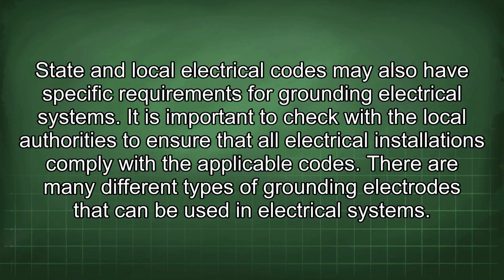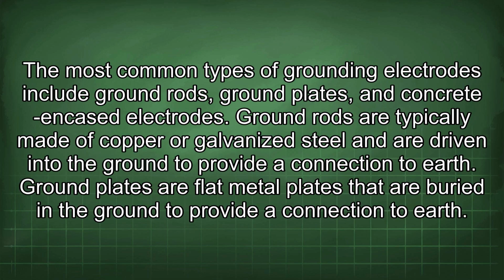There are many different types of grounding electrodes that can be used in electrical systems. The most common types of grounding electrodes include ground rods, ground plates, and concrete encased electrodes. Ground rods are typically made of copper or galvanized steel and are driven into the ground to provide a connection to earth. Ground plates are flat metal plates that are buried in the ground to provide a connection to earth.